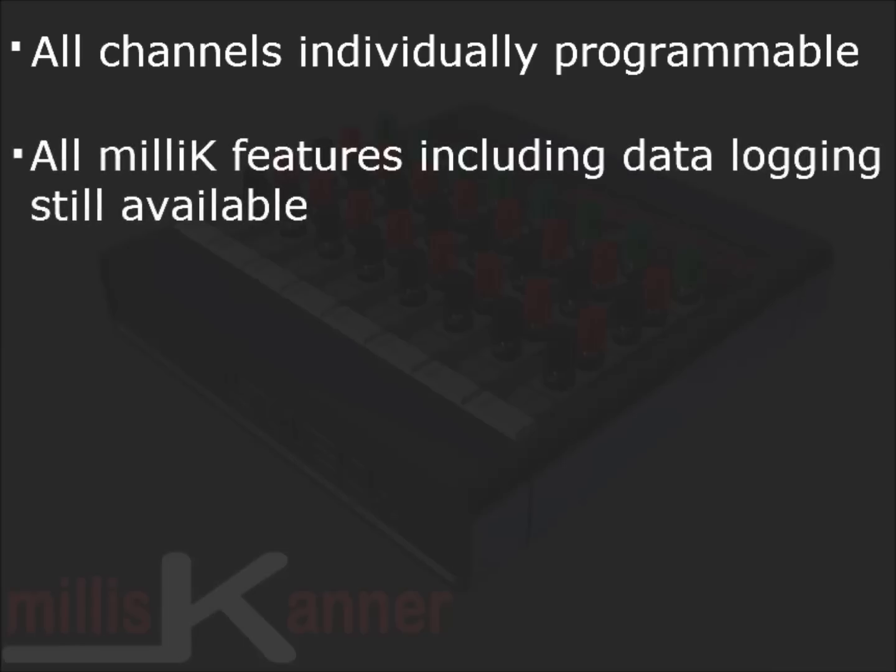The channels are all individually programmable, and any channel can be configured for use as an SPRT, a PRT, a thermistor, or a thermocouple. All the milliK features, including data logging, are available on all the new channels.